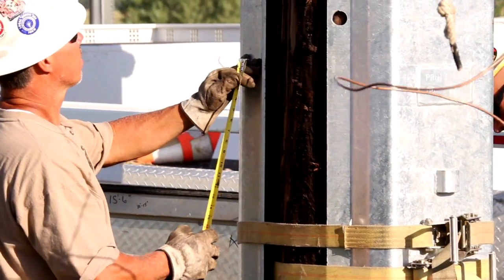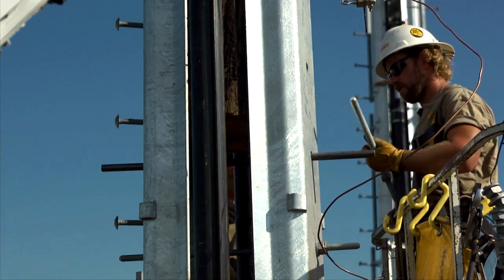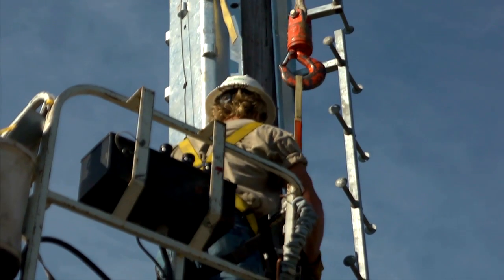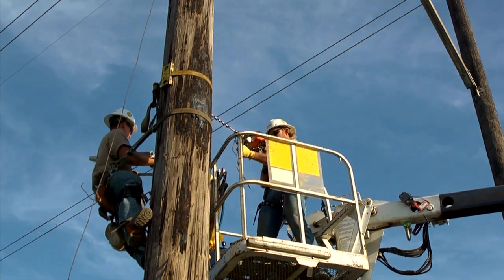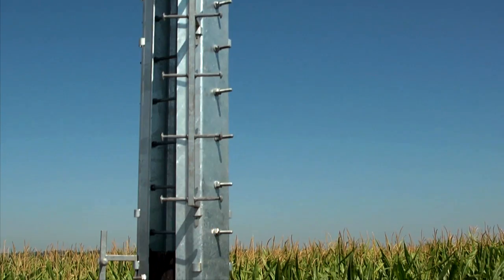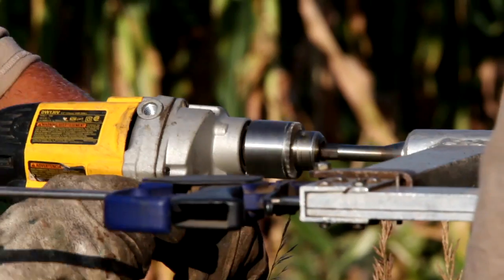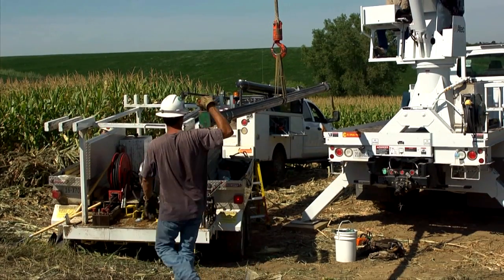This short video shows how one Midwest utility chose to remedy their 345 kV conductor clearance points of interest using the Phase Razor Structure Lifting System. This same utility has also raised more than 90 energized 161 kV structures at an installed cost of just 30% of structure changeout costs. An experienced line crew with minimal training is able to safely raise multiple structures per day, saving the utility thousands of dollars and often completing the work ahead of schedule. Line crews receive training from an LWS field demonstrator and are typically ready to perform lifts after just two days of training. Installations can be performed either by the utility's own crew or by an experienced line contractor. LWS also provides a special lifting equipment and tool trailer that is available for lease or purchase.